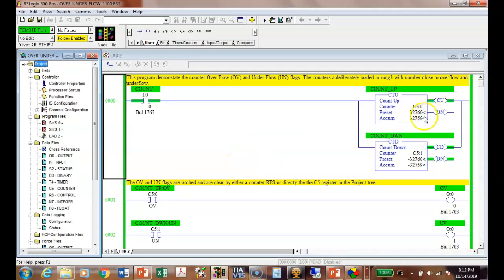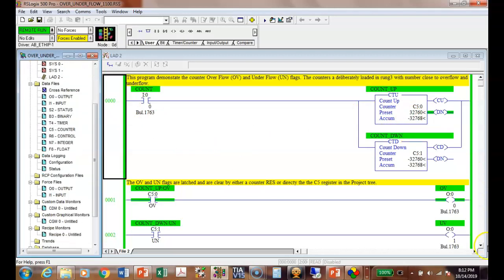So I'm starting out putting numbers in this guy, right? So up there already I have, what am I using to make them count? I'm using switch 0. 37, okay. So notice what happens to it. What happened to my sign? Yeah, it was positive, right? And changed what? Negative. And what happened? Well, the overflow bit went true, and I'm turning on the light.